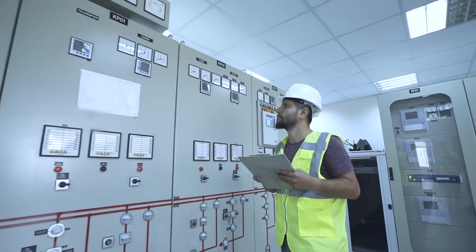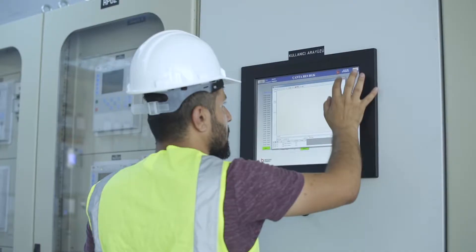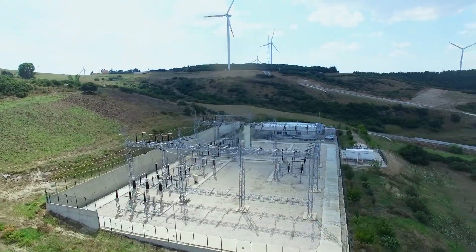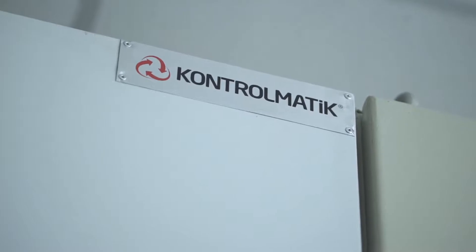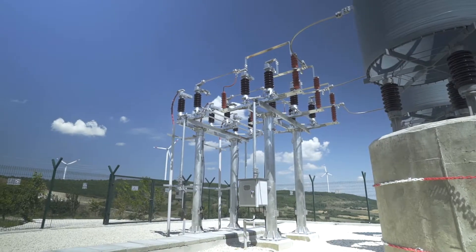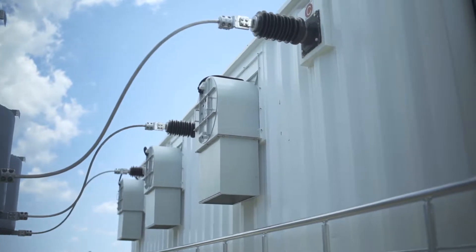Control systems can be communicated and coupled to the existing system to operate in a coupled manner, allowing quick and reliable control of line voltages and providing dynamic, fast, reactive power following system conditions. With the SVG system, transfer capacity can be increased, losses in active power oscillations can be reduced, and over-voltage can be prevented during load loss.